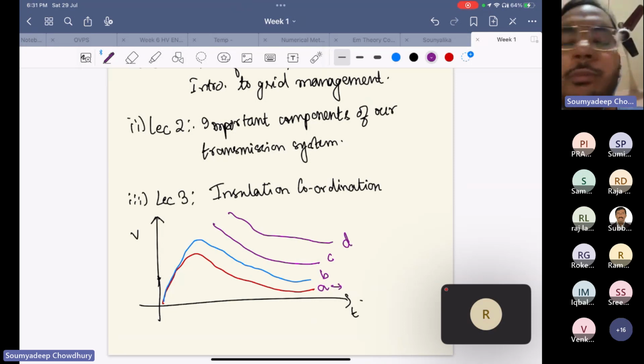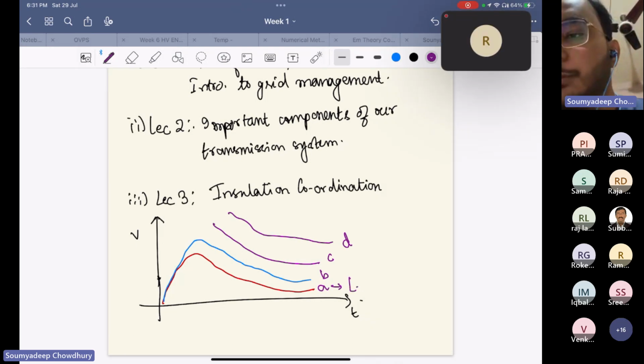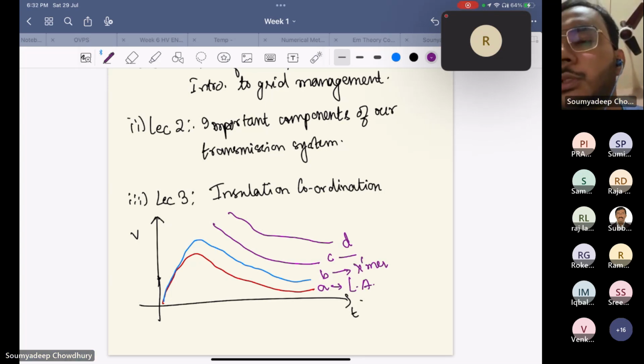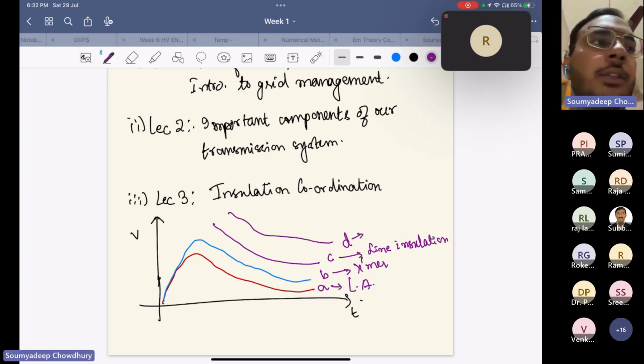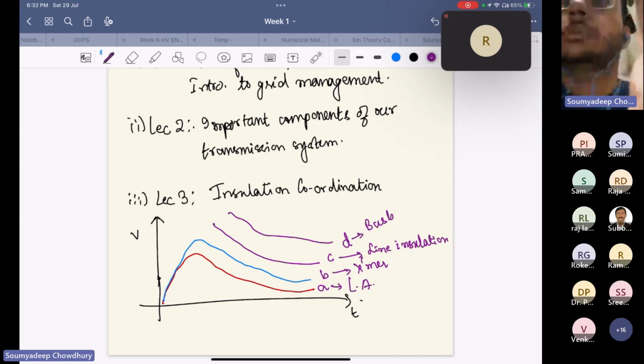So the lowermost curve corresponds to the lightning arrestor. This will correspond to a transformer. This will correspond to your line insulation. And this will correspond to the most valuable equipment, which is the bus bar. The insulation of the bus bar is the most valuable, and we want to protect that.